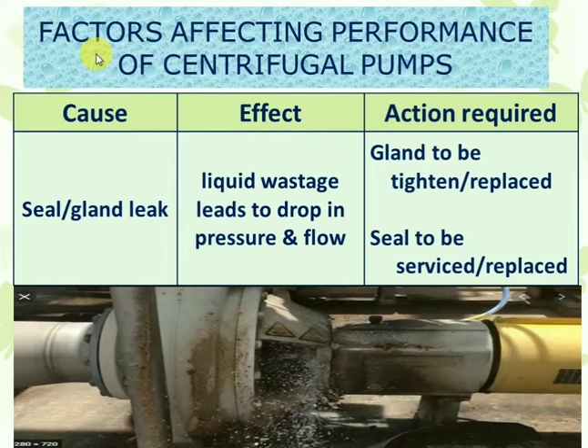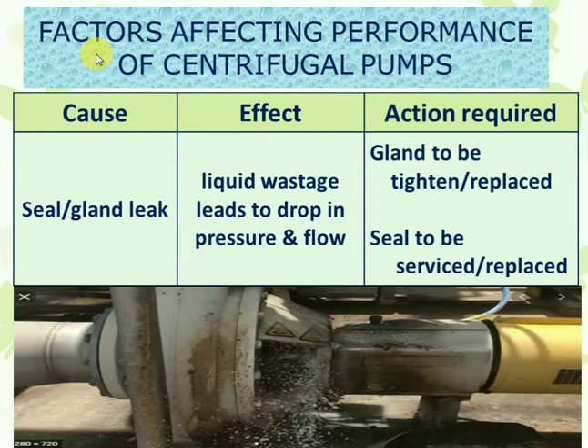In the LLF check, we will look for any abnormal noise from the pump, bearing, or motor, and any leakages from flanges, seals, or gland. In gland packing, a drop-by-drop water leakage coming out is allowable in order to ensure the gland packing healthiness. If we over-tighten it, the gland packing will get damaged and smoke will come out. So this drop-by-drop leakage in the gland packing is allowable.